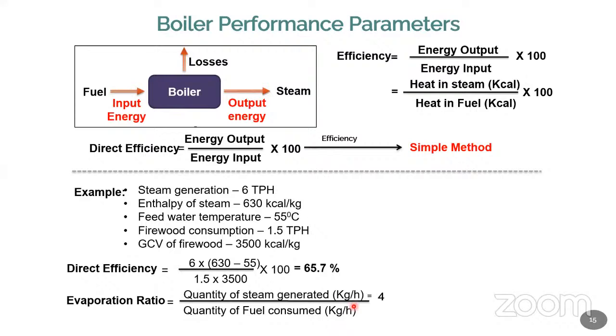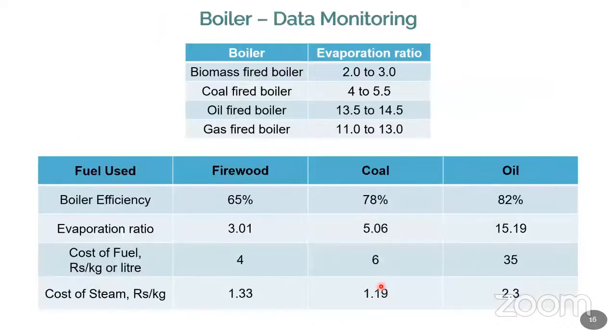This is the first important point. Suppose it is very high, that is not possible. More than 5.5 is not possible. So there is a problem in measurement, whether in the fuel or in the steam; you are not having a proper measurement. So by measurement, we can come to a conclusion whether your system is correct or wrong, or whether your measurement is correct or wrong. That we can find out.